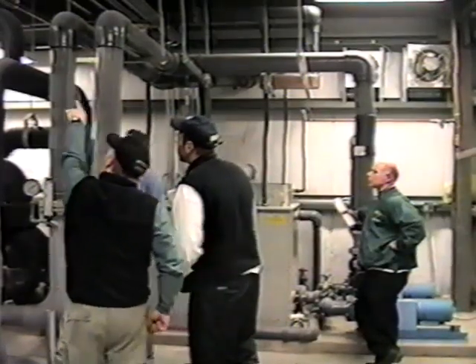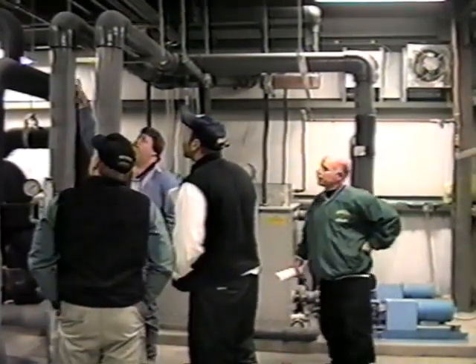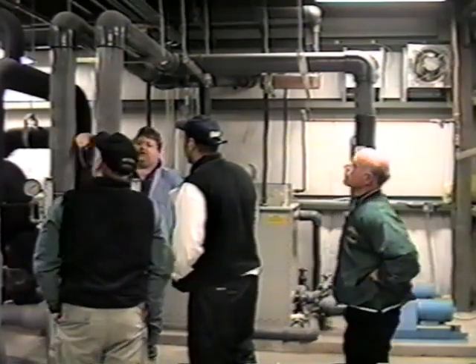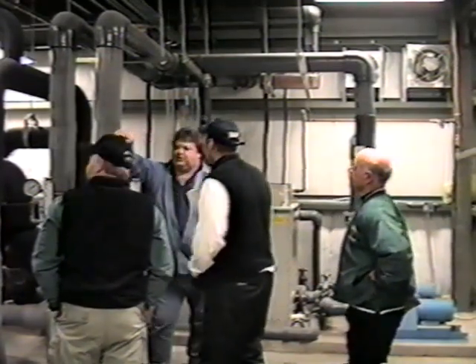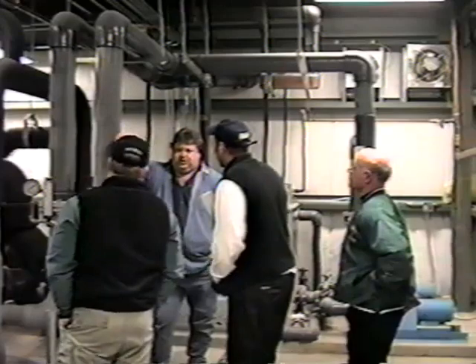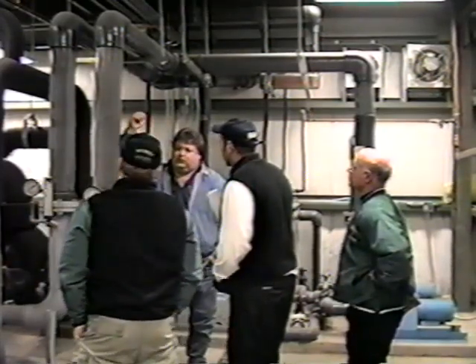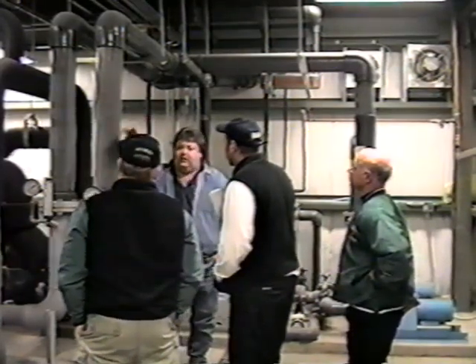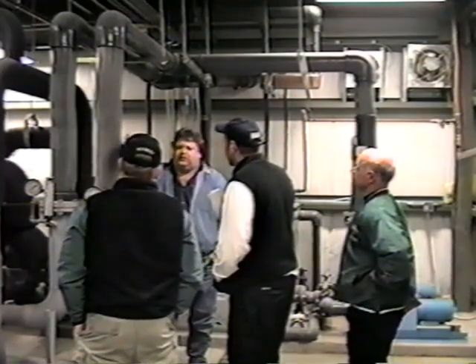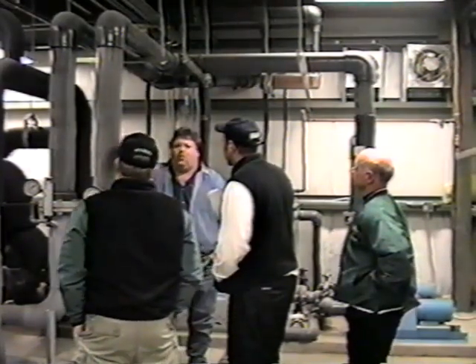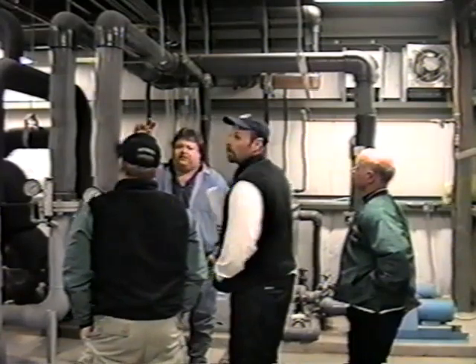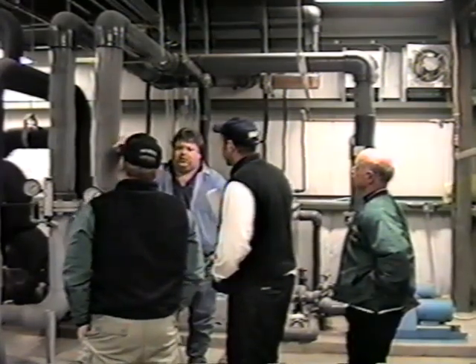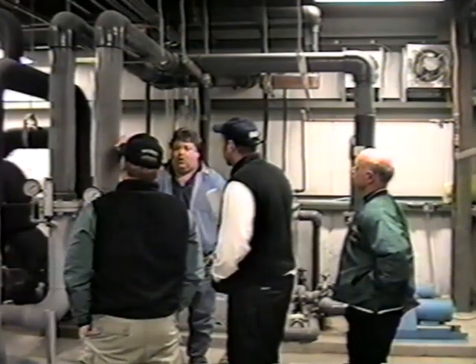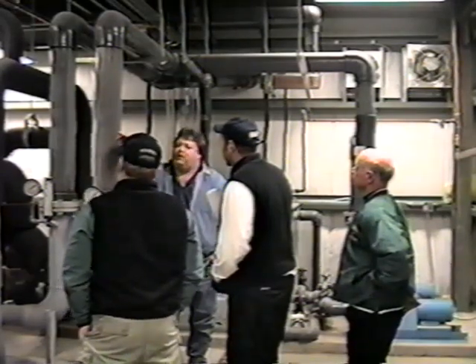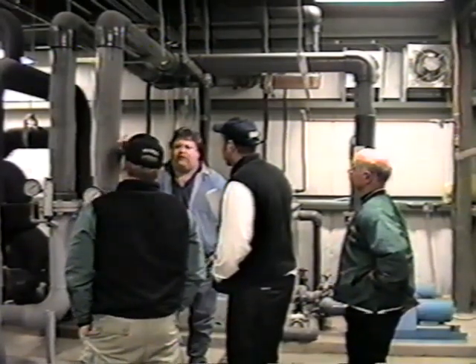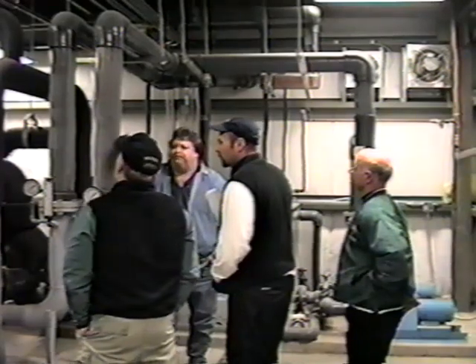This is the refrigerant leak detector for the vent lines. If for some reason one of the chiller circuits blew a high pressure relief due to lack of water in the condenser or whatever, and the safeties didn't pick it up, the pressure safety should shut your chiller down way before that. If for some reason it didn't though, you've got pressure reliefs on your vessels that will blow so nothing explodes or anything. It's really more for fire protection than anything.